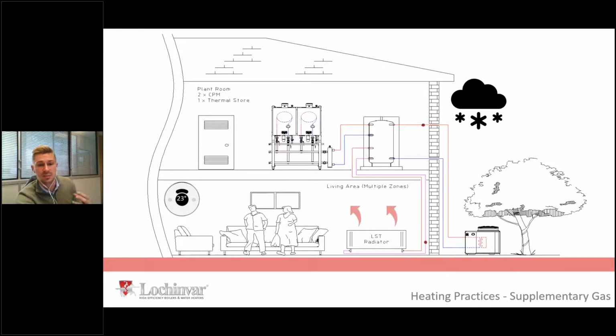And then what happens is the boiler will basically kick in because the air source heat pump sat there running at 100% rate. It knows that the thermal store is still depleting in temperature, even though it's putting in as much as it can. So at this point in time, it's under spec. It's working as a baseload product. The gas-fired boiler will turn on. That's going to be one of our CPM boilers. So it'll have a 10-to-1 turn down ratio on it. So it'll input about 5 kilowatts. It won't dominate your heating load. Top up that thermal storage volume, and the user isn't going to be affected. The building emission rate is reduced. The building gets planning. Everyone's happy.